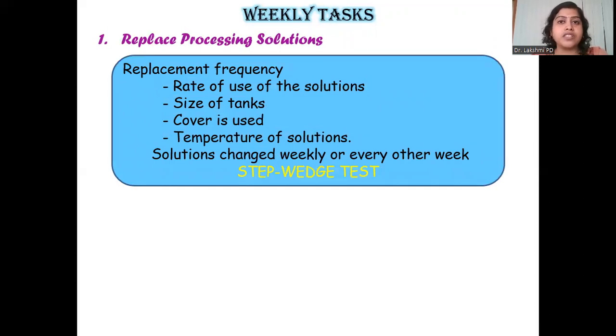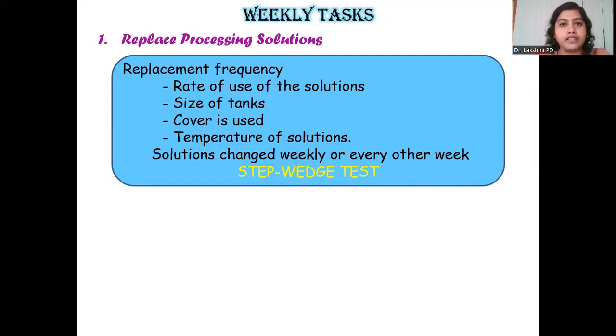Moving on to your weekly tasks. The first is replacing your processing solutions. Check the levels every single day, and replace on that particular day when needed. Otherwise, ideally at the end of two weeks it is always recommended to change your processing solutions, as they become depleted by oxidation or overuse. The replacement frequency is determined by the rate of use: in a facility with only five to six radiographs per day, two weeks or slightly more may be sufficient; but if 100 to 150 radiographs are processed daily, the replacement frequency would be much shorter — perhaps one week or every five days.